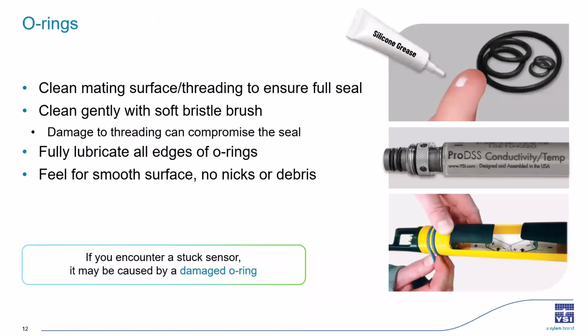So let's talk about O-rings for a second. They are all over your instrument, at the connectors, on the sensors. So first, let's make sure to clean the mating surface, and that's the groove where the O-ring is sitting. If there's dirt in there, you won't get a full seal, and it will allow moisture to get in. So you can clean the threading and the O-ring gently with a soft bristle brush. And then to remove O-rings, always just use your fingers to pinch them up and grab them out, rather than using a tool. If you're using a screwdriver or anything to leverage the O-ring out, it could damage the mating surface and damage the seal.